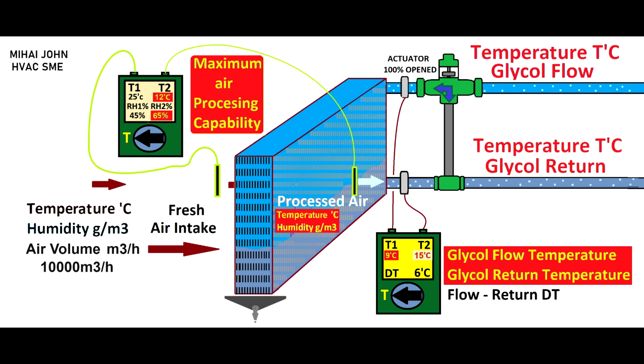In this case, the engineering team is currently conducting an in-depth investigation into potential fault associated with elevated glycol flow temperature. It is essential to clarify that attributing a fault directly to the air handling unit might not be accurate, especially when the glycol is sourced from a third party. The issue could lie within the chiller system, impacting the AHU heat exchanger functionality. It relies on chiller water temperature to effectively cool the air that passes by.